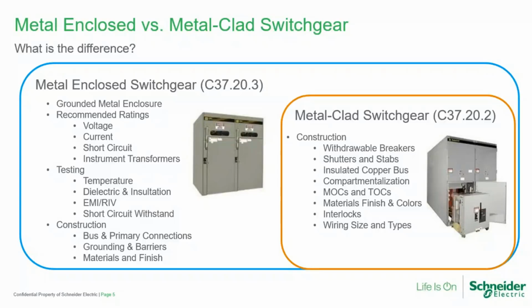Metal clad switchgear actually piggybacks on top of the metal enclosed switchgear standard and takes it much further in terms of the construction requirements. So if you ever wondered why most manufacturers' metal clad switchgear looks very, very similar, this is why. It's because the metal clad standard is very much a build standard. It explains how to build metal-clad switchgear and how it needs to be built. Certain things like withdrawable circuit breakers, automatic shutters and stabs, insulated copper bussing, compartmentalization, the requirements for MOCs and TOCs, and the materials and finishes, and the wiring sizes and types for all of the control wiring, are all laid out type for type and exactly how they need to be installed and constructed in the metal-clad switchgear standard.